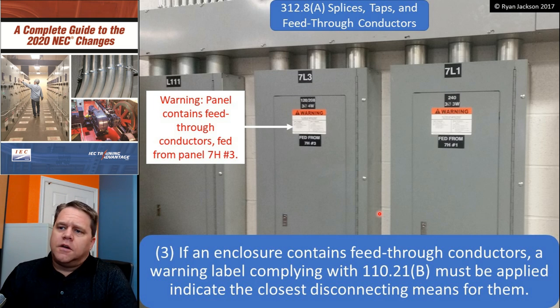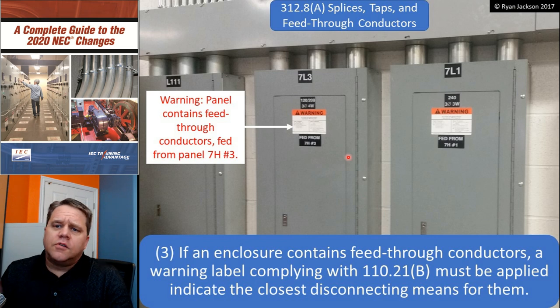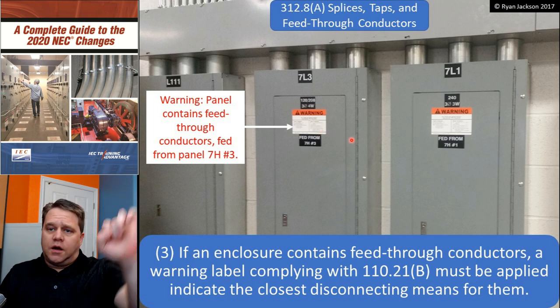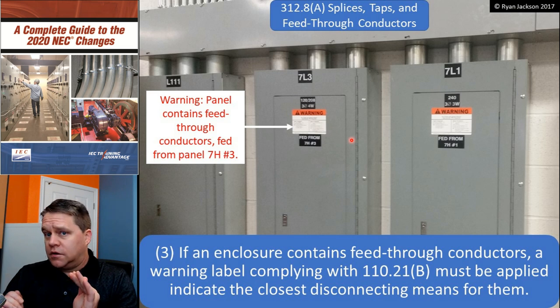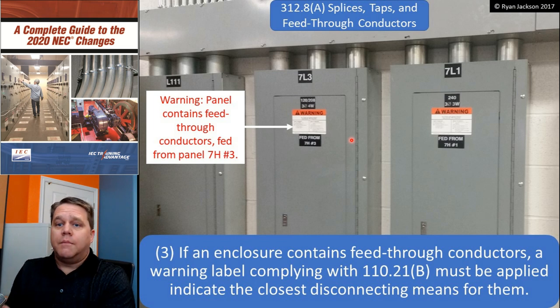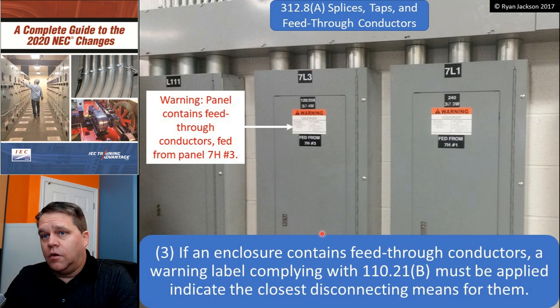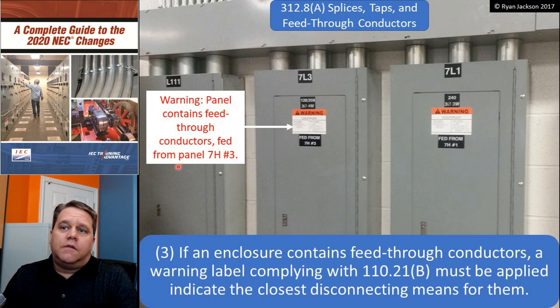Item A3 — I think this was added back in 2011 and it's a good rule: if an enclosure contains feed-through conductors, a warning label complying with 110.21(B) must be applied to indicate the closest disconnecting means for them. The idea is: if this is a main breaker panelboard and I shut off the main breaker, everything in that enclosure should be de-energized. If feed-through conductors remain live, a label should warn me — for example: 'Warning: panel contains feed-through conductors fed from Panel 7H, Circuit 3.' That tells me how to shut them off.